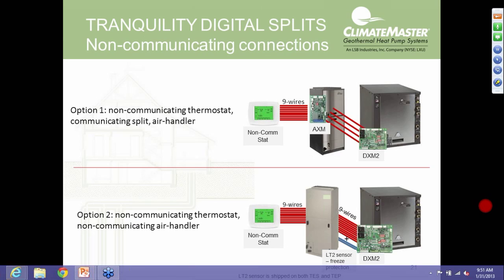And then option 2 shows a non-communicating air handler, showing we can also do conventional inputs from the DXM2 board to our conventional air handler, and then on through to the conventional thermostat. It'd be a similar setup if we were doing a dual fuel with a gas furnace with our split.